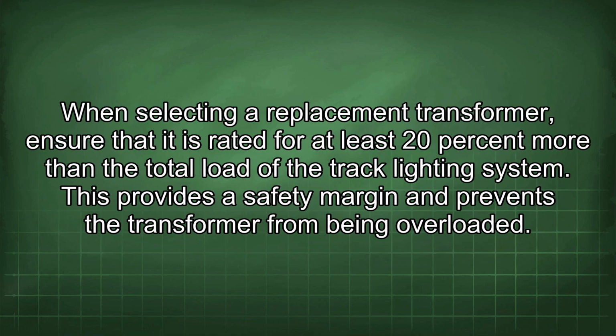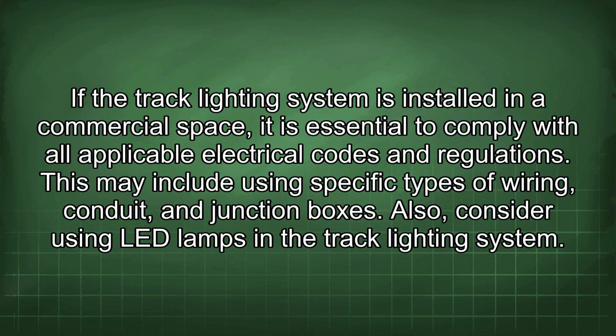When selecting a replacement transformer, ensure that it is rated for at least 20% more than the total load of the track lighting system. This provides a safety margin and prevents the transformer from being overloaded. If the track lighting system is installed in a commercial space, it is essential to comply with all applicable electrical codes and regulations. This may include using specific types of wiring, conduit, and junction boxes.